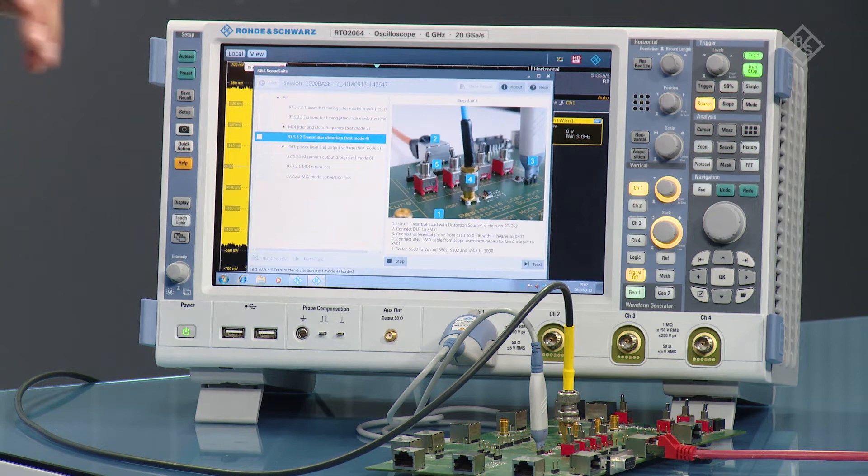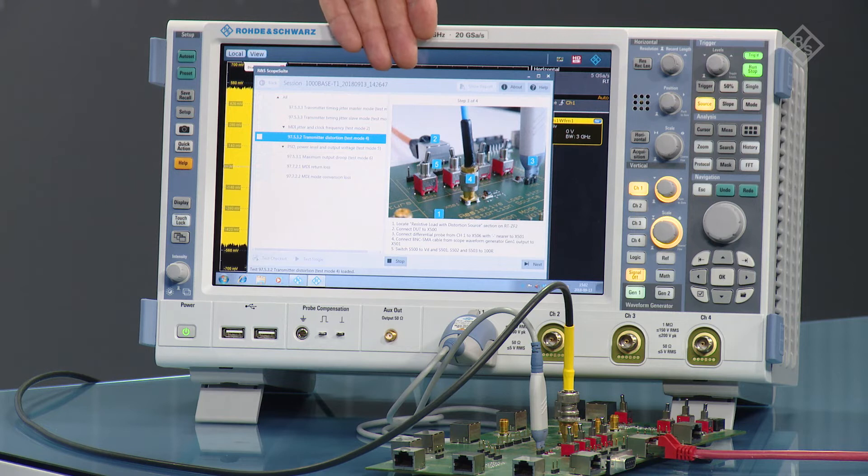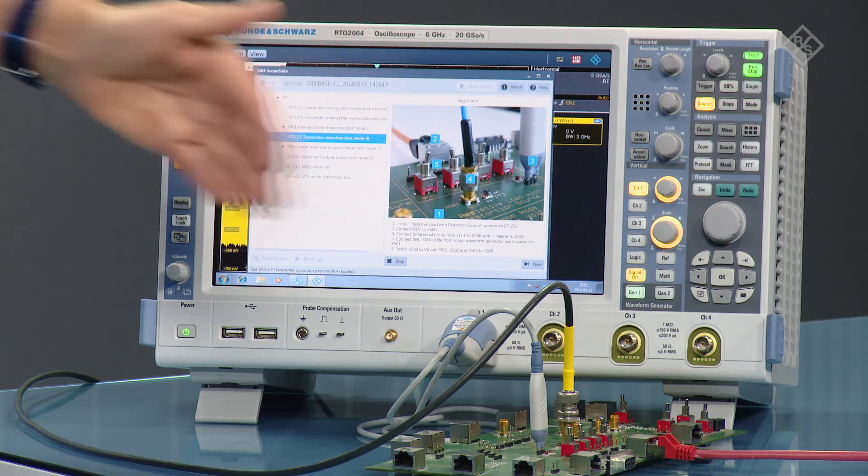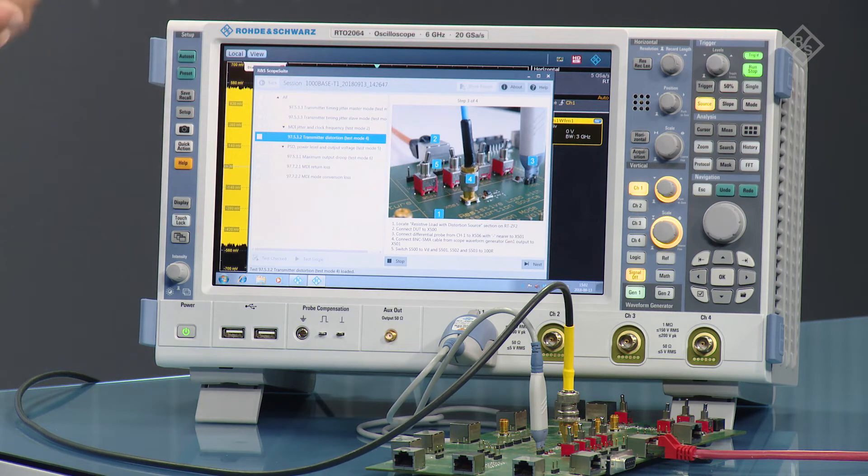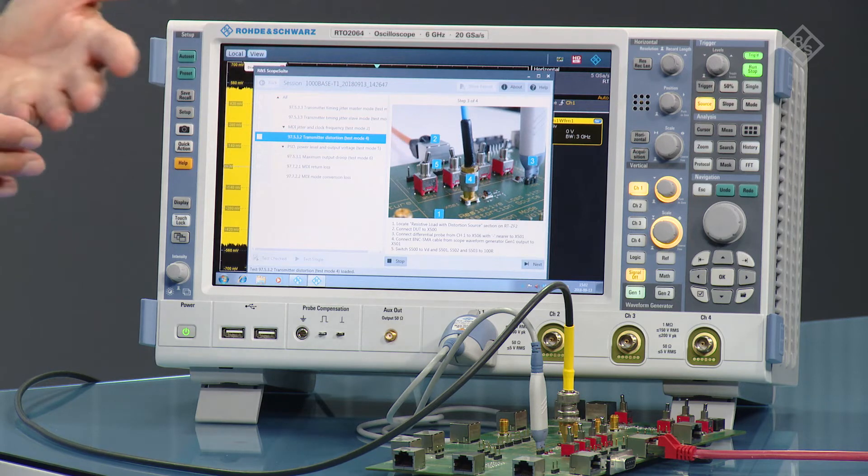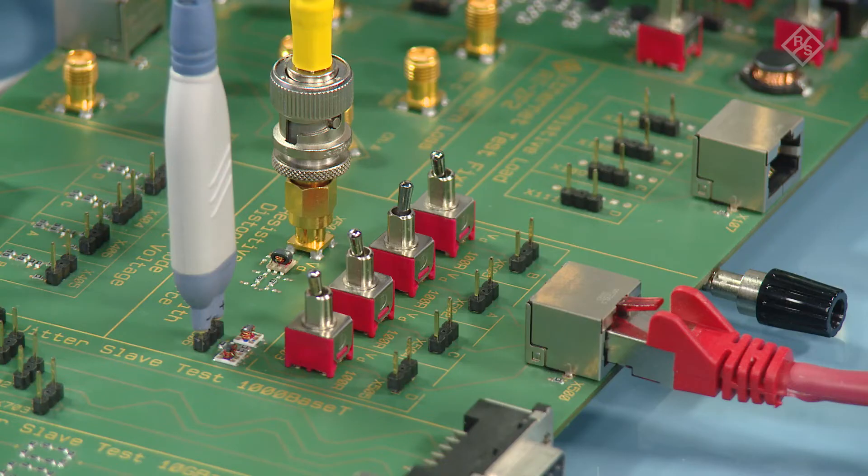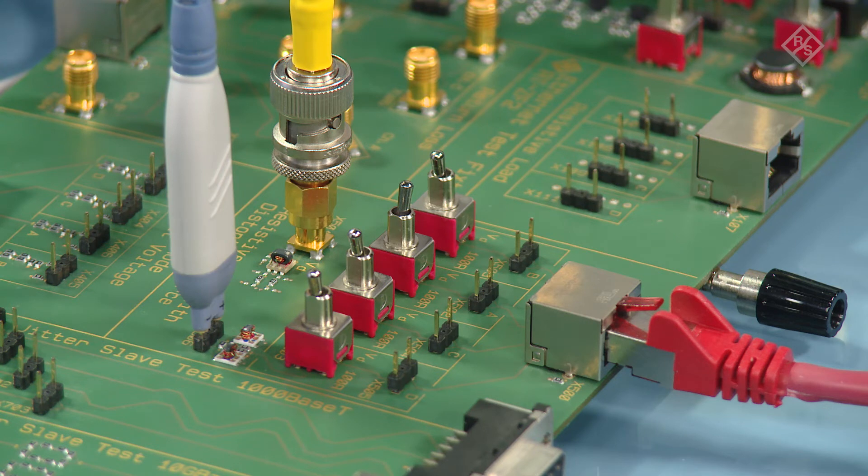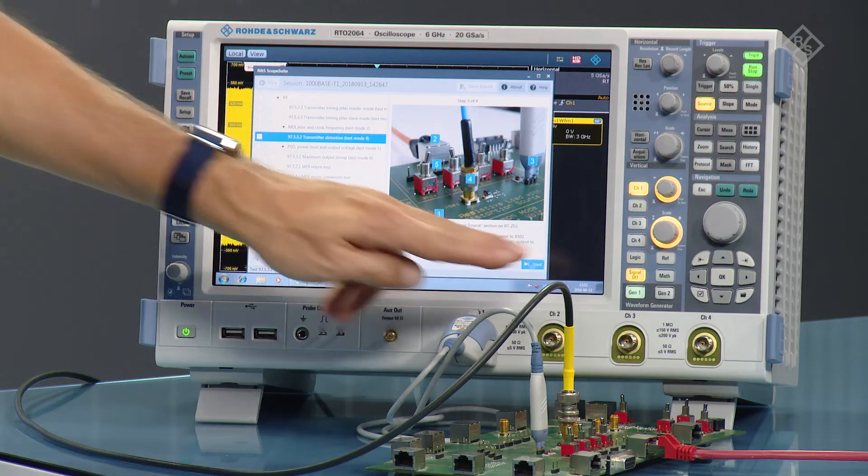And now you go through a series of guided steps. The first thing is a picture describing how to set up the compliance test for distortion test with disturber. And you see all the connections match exactly to what I have done beforehand here. So press next.